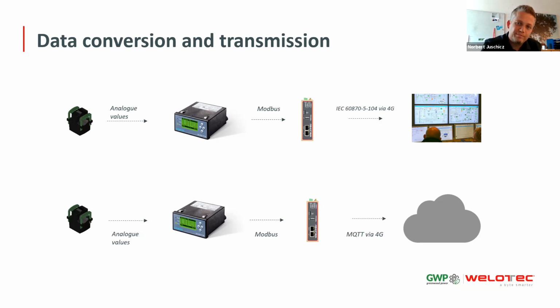Thank you very much, Norbert. So we now have seen that we get analog values into the FCM, and then we have serial Modbus. So it's usually RS-485. And this Modbus can now be converted and transmitted. So what we need to do is convert the Modbus into a protocol that is also a good protocol for northbound communication, for example, over a cellular network or over ADSL and fiber. And this is definitely not Modbus.